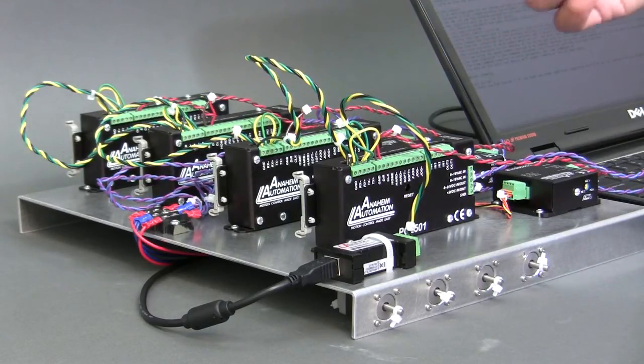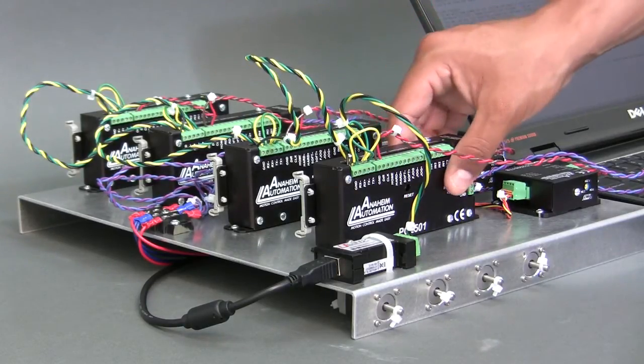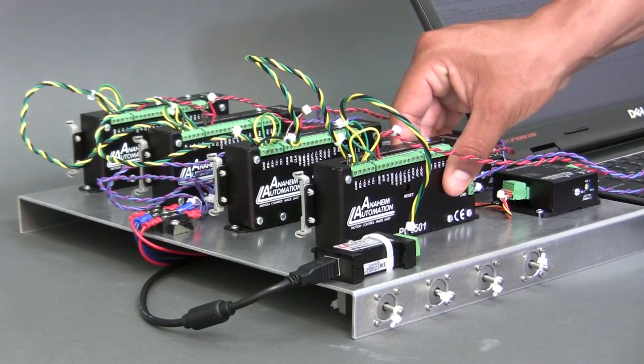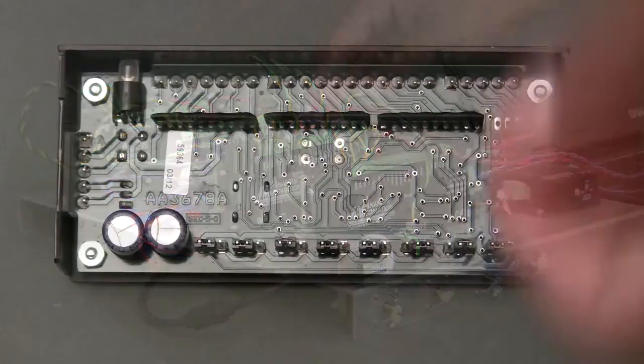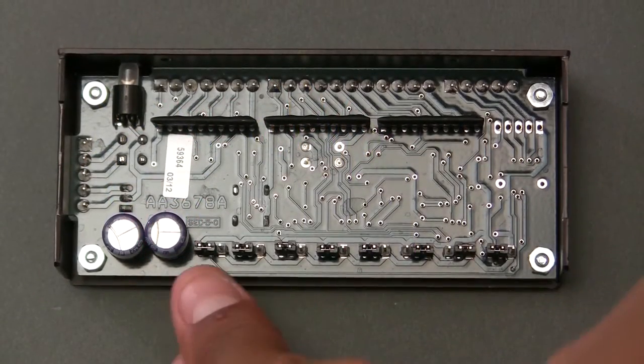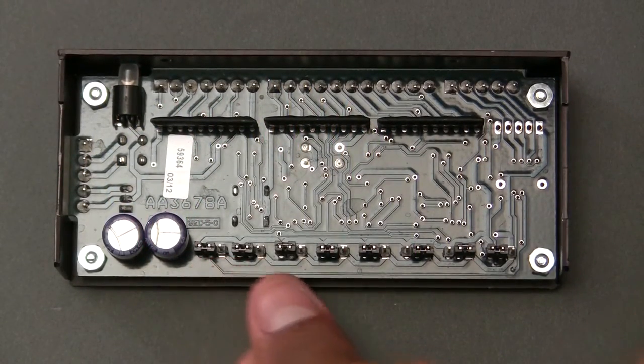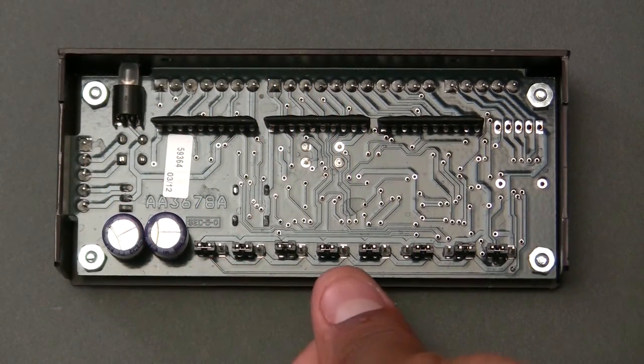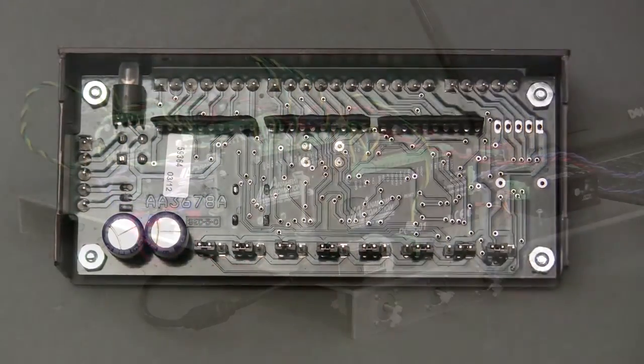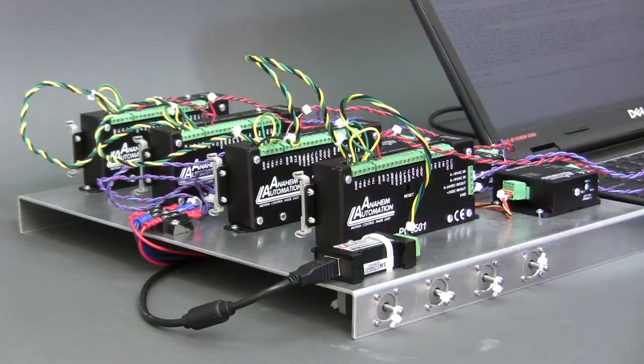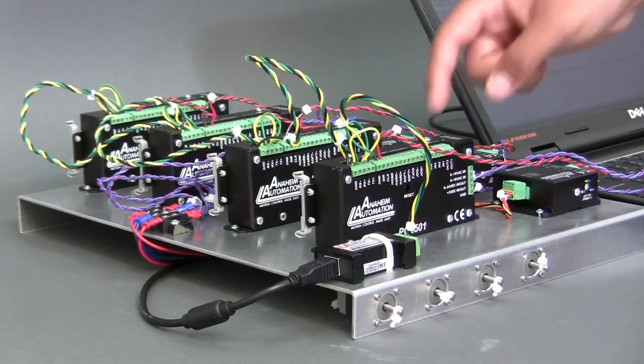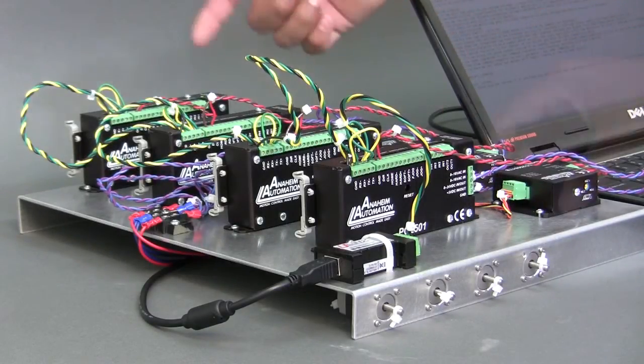The PCL501s need to be manually set with unique addresses. To do this, remove the back plate from the units and set jumpers JP4 through 8 accordingly. These four PCL501s are address 0 through 3.